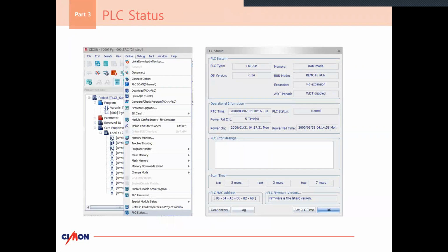When I want to look at the PLC status, this is more for troubleshooting or checking the features of your PLC in terms of firmware and other real-time clock features. We'll see the firmware or OS version right here. This is upgradable for free, and unlike other competitors, you can revert the OS version. With Allen Bradley, for example, if you go up too high in revision, you can't step back down - you just ruin that hardware and have to buy a new piece of equipment.